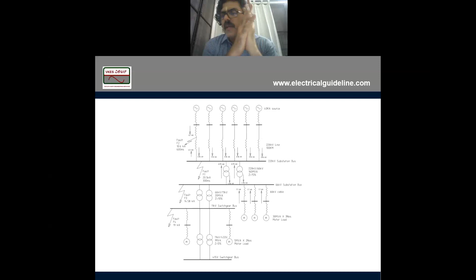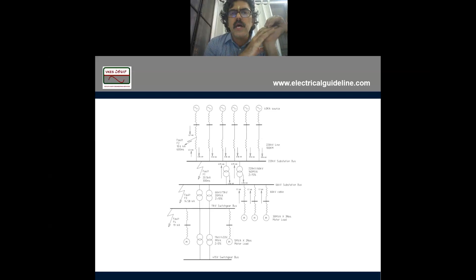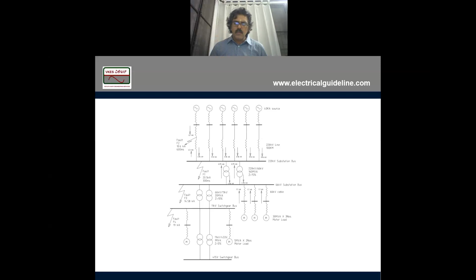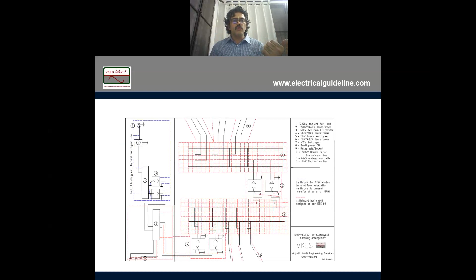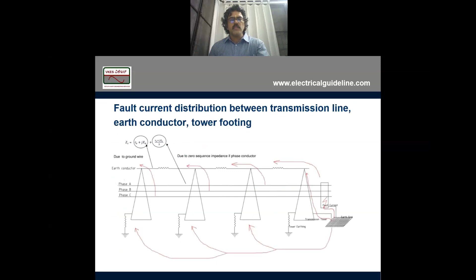You have a single line diagram, and the first step for any substation earthing design is the input. The input is the fault current calculation. You can do either hand calculation or use ETAP, or anything else, and get the fault current values. Once you get the fault current value, next you determine what fault current will flow through the earth grid. Not all the current will flow through the earth grid.